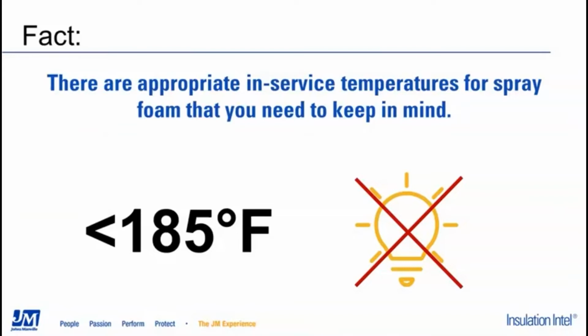What will happen is if that can light is outfitted with an incandescent bulb, it will probably run for no more than 30 minutes at the most before it trips an over temperature switch. Certainly not much of a problem when those can lights are outfitted with LED or CFL bulbs, but with an incandescent it will certainly happen. There is an in-service temperature rating for, we'll just call it medium density closed cell spray foam, and open cell spray foam in general, of 185, 190 degrees. Perhaps through specialty formulations, we could get through 205, maybe 210 at the most, but you're really not going to see a thermoset polyurethane foam that can be installed in direct contact with something that's seeing daily in-service temperatures of over 200 degrees.